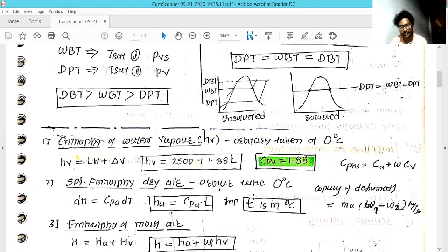So now we are ready to find the enthalpy of moist air, which is the combination of air plus the water vapor. If you put the above values into it, H equals HA plus the specific humidity multiplied with the enthalpy of the water vapor. Enthalpy is a function of temperature in the ideal condition. So the formula turns out to be CPA into T plus the specific humidity W times (2500 plus 1.88 into T). With this, we can find the enthalpy at a particular location. Keep in mind that the temperature is in degrees Celsius.